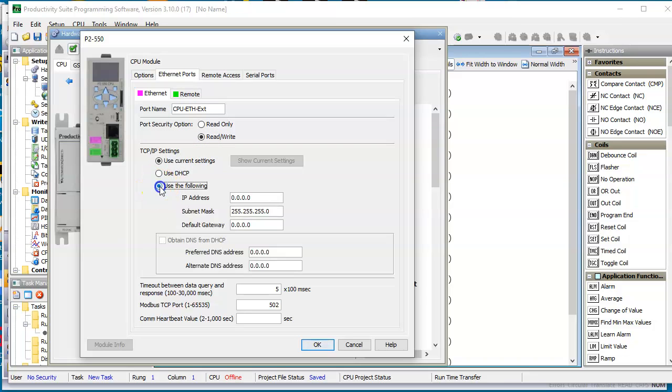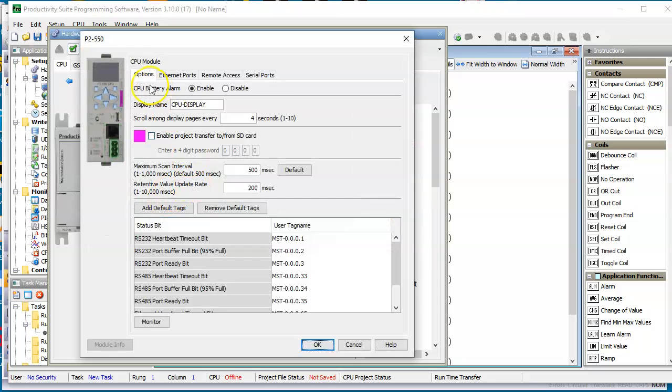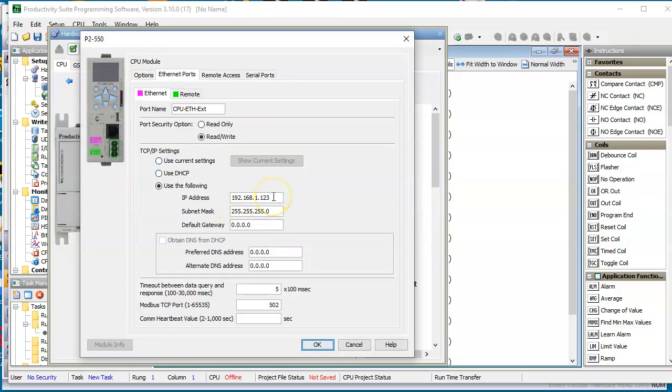And in this case, I'm going to set the IP address of the unit. I'll set it to be 192.168.1.123, for instance. Whoops, I hit enter by accident, so let me go back to there. I want you to notice that on this screen, with the read/write here and down here, the Modbus TCP port is already declared as 502, which is the standard. So that's correct, and that's already turned on. You want to make sure that you've got the access here set to read and write.